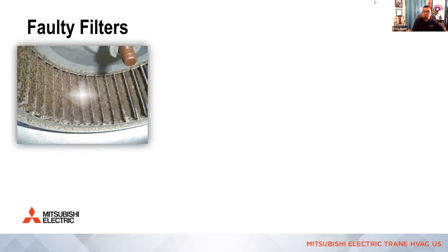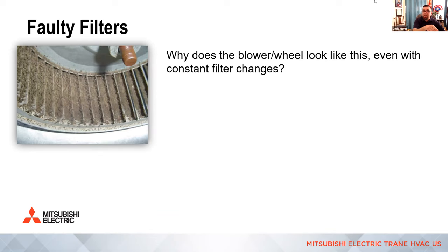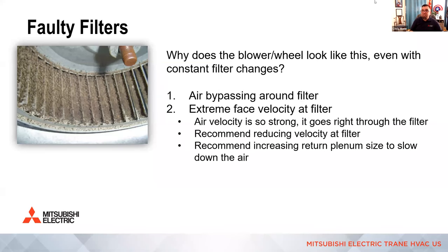Obviously, filters can cause some airflow problems. And the reason I bring this up is because it's a good indicator of velocity issues. If we see blower wheels in standard air handlers look like this, if the filter is clean and the blower wheel looks like this, chances are the velocity of the air is so high that it's bypassing the filter or going right through it. And I've seen this a lot on ECM furnaces, when the ductwork was not modified for the larger volume of air that's needed for that furnace compared to the old inefficient 80%. Extreme face velocity, what ends up happening is it almost eats the filter away. I've taken filters out of furnaces and almost seen right through a MERV 7 blue filter because the velocity was so high, it just deteriorated that thing.